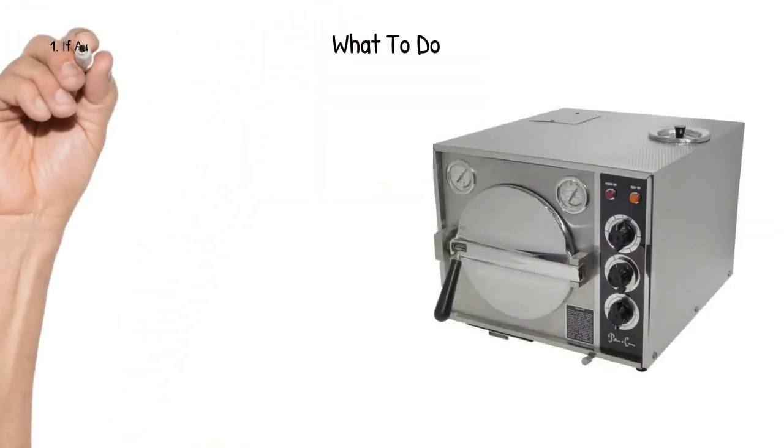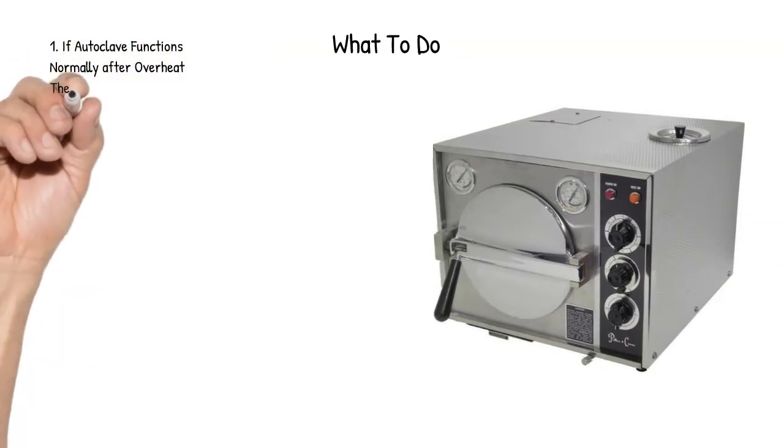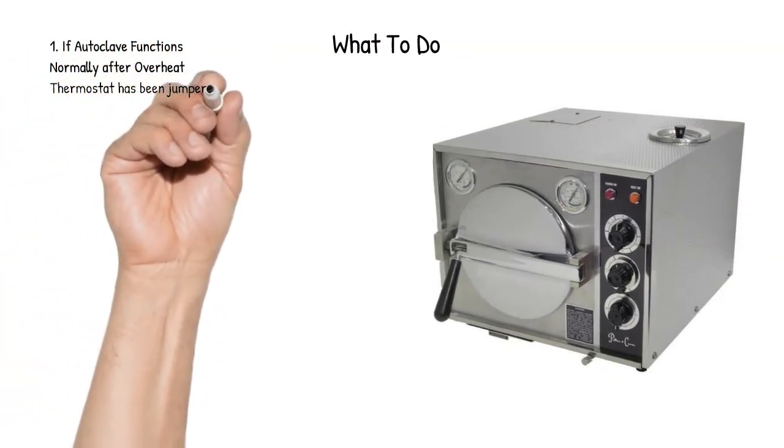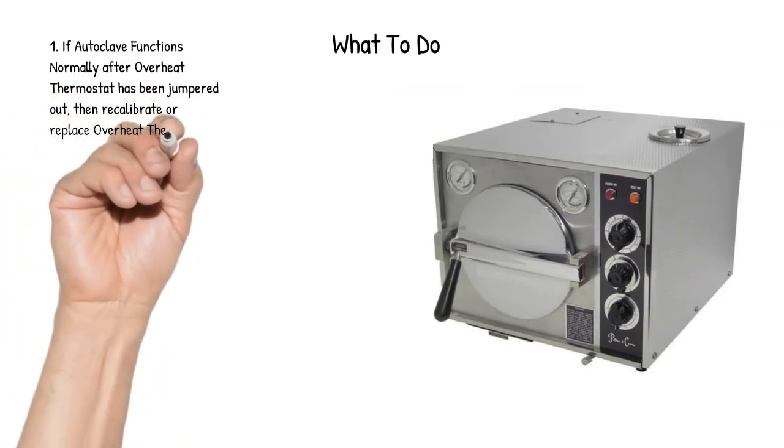What to Do: 1. If autoclave functions normally after overheat thermostat has been jumpered out, then recalibrate or replace overheat thermostat part #PCT042-058.